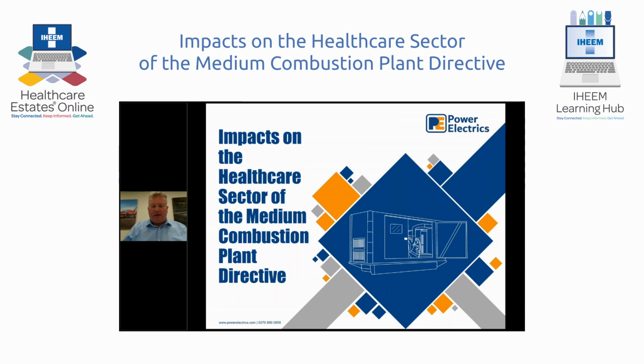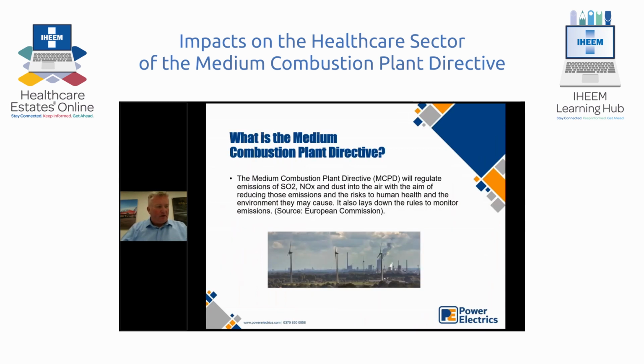Now we move on to the explanation of what the Medium Combustion Plant Directive is. Back in November 2015, the European Parliament signed the directive, which aims to reduce the amount of sulfur oxides, oxides of nitrogen, and particulate matter or dust in the atmosphere. This is for equipment between 1 megawatt thermal and 50 megawatt thermal, and doesn't include the larger stuff associated with power stations. It came in back in 2015, and you'll see timescales later in the presentation of how the UK have adopted this and where we are at this current point.